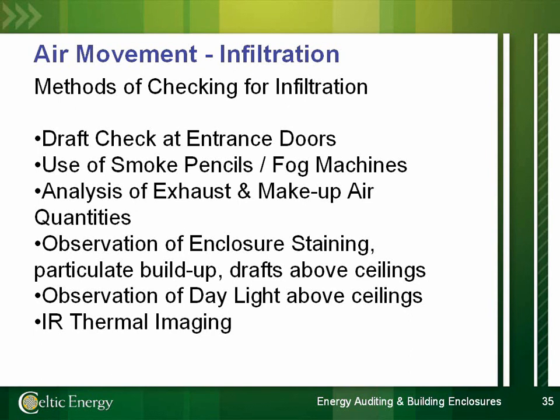Theatrical fog machines can create a large cloud of non-toxic smoke that can give you a very excellent visual impact and image of where air is leaking into or out of a building. We can do a paper study and look at the balance between exhaust and makeup air quantities for a building. If there's current data, this always has to be taken with a grain of salt if you're looking at original design drawings, because things will invariably change over time with a building. And likewise, you can look for various telltale evidence in the visual observation of the building in the interior and exterior.